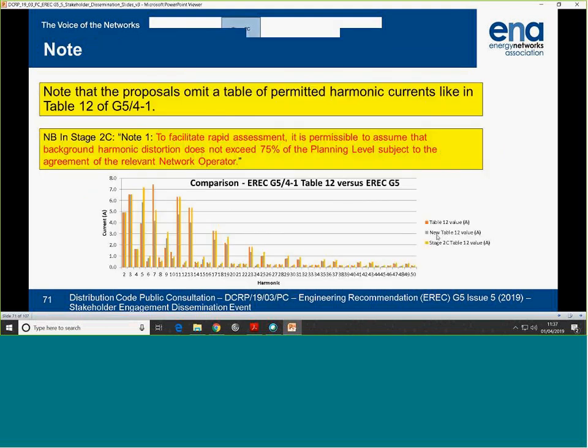Which takes me to this one. For the sharp ones in the audience, they would have noticed that table 12 of G5/4 is missing, just like we lost table 7. And then, as you can see, we've covered the possibility of a quicker assessment by allowing it to be done at stage 2C. The background level is at 3/4 of the planning level. And the table values show that you've still got the fifth higher, the seventh is lower, the 11th is the same, the 13th. So in this case, that's okay, I think.